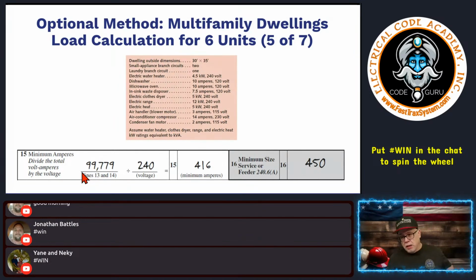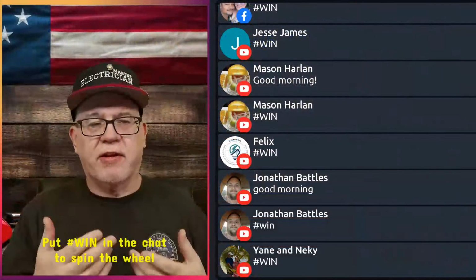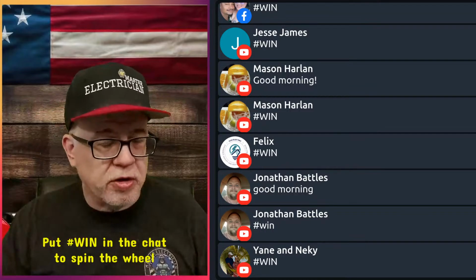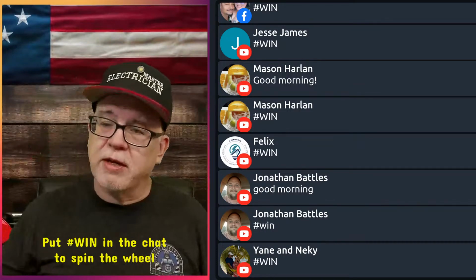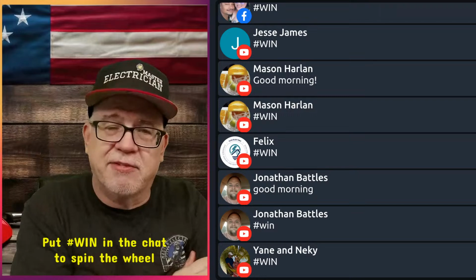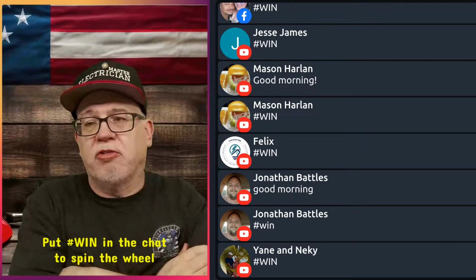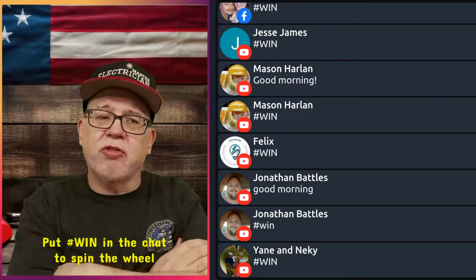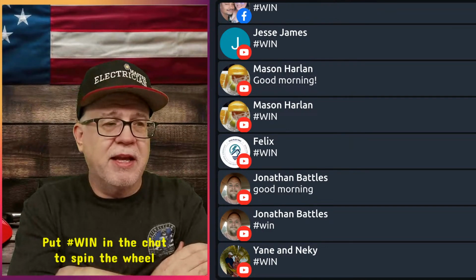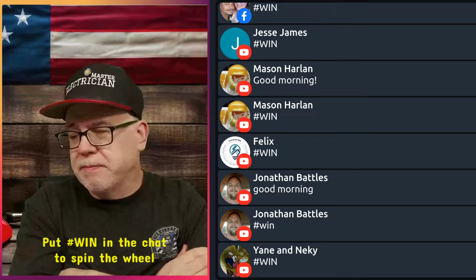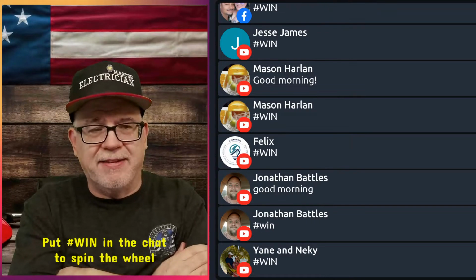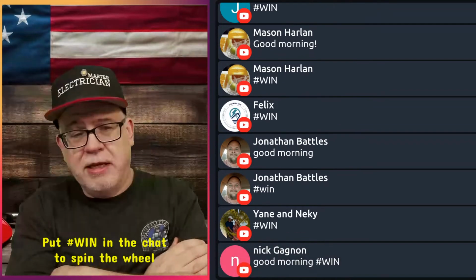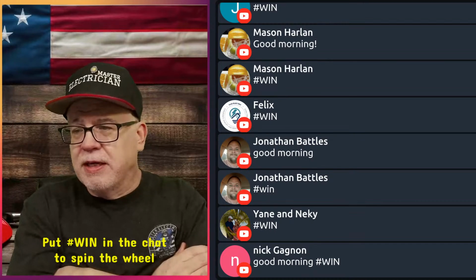Now, the one thing about the optional method is that we get away from all of this other stuff about looking for the largest motor, that 125%. We get away from all this. So this is why, obviously, in the field, you're going to use the optional method. There's no doubt about it. Although if an educator tells you that you never need to learn the standard method, they are full of poop, and don't listen to them. And I hate to say that about fellow educators, but if they say that, they're full of poop.